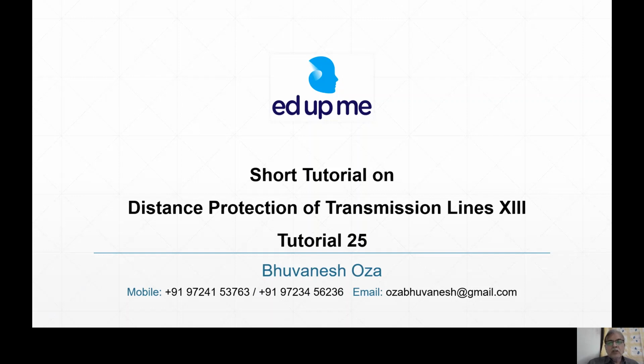In tutorial 12, distance protection tutorial 12, we have calculated one numerical. Here we are calculating another numerical which is similar but reverse. Reverse in the sense, now here we will be giving the values of K1, K2, K3, zone 1, 2 and 3 settings, and you will be required to find out the relay reach.